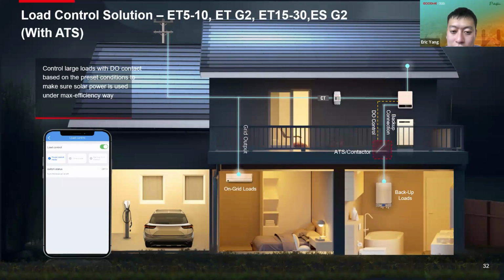And if the customer wants to control loads that are not special, normal loads that do not have a communication port, meaning the inverter cannot connect a communication cable to the load directly, then the customer can install an ATS, because all the ATS have a communication port that can connect to the inverter's DO control directly. The inverter can send a command to this ATS, and the ATS will turn the loads on or off by turning the power cable on or off. Okay, that is the difference between with ATS and without ATS, because the customer may want to control different loads.